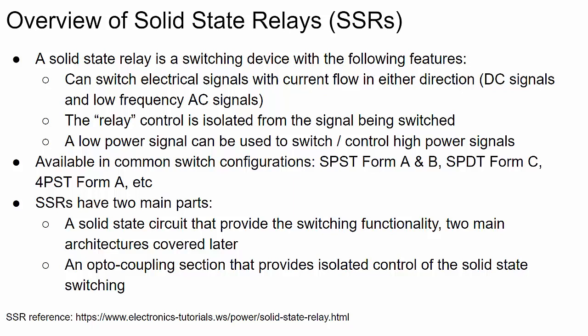A solid state relay is made up of two main circuit parts. The first is the optocoupler — they typically have some type of LED inside, and sending a control signal through that LED actuates the solid state switching device. The optocoupler section isolates the control signal, and the optical signal it creates biases the solid state devices to either open or close the switch.